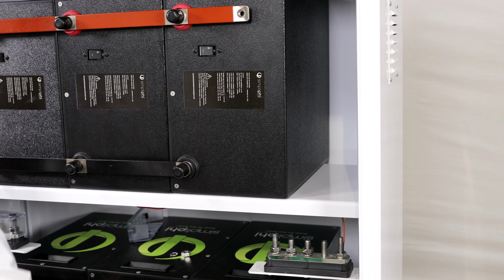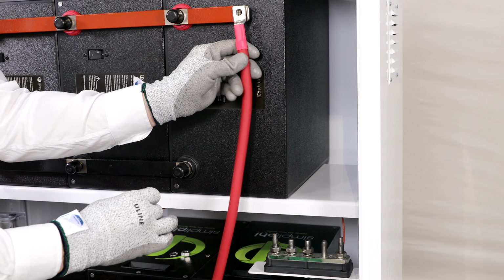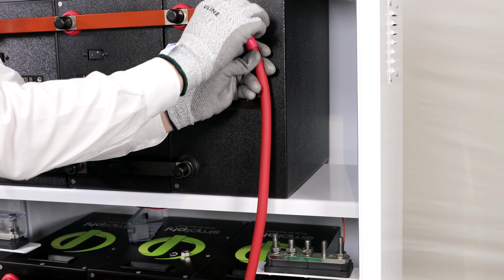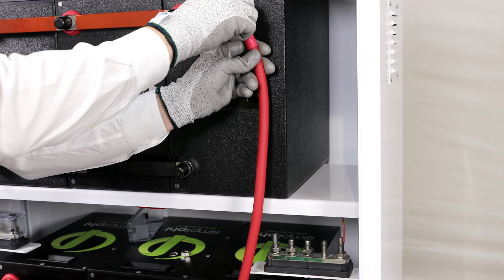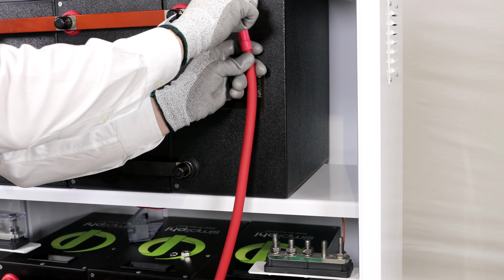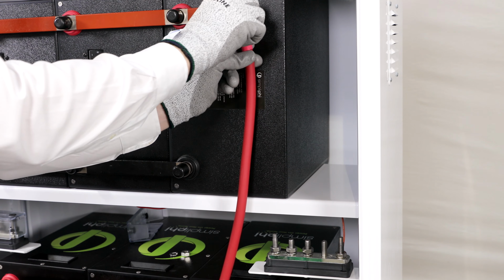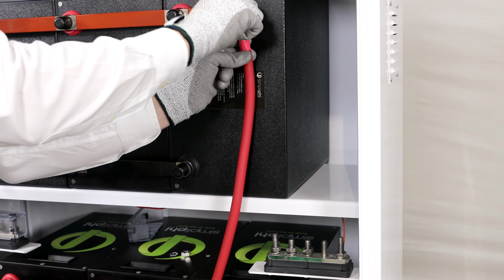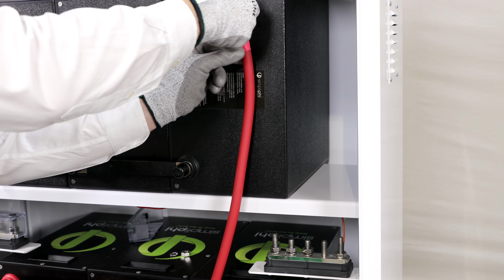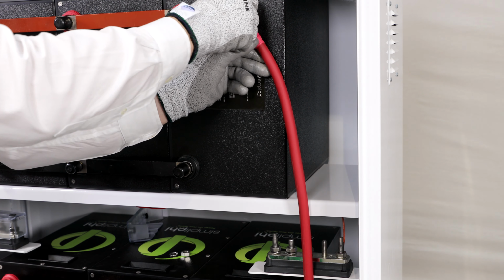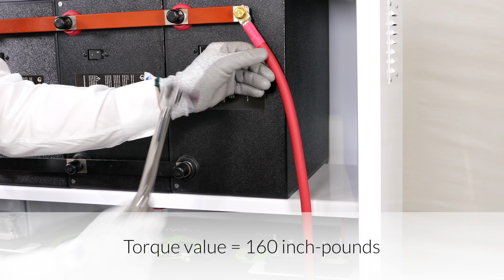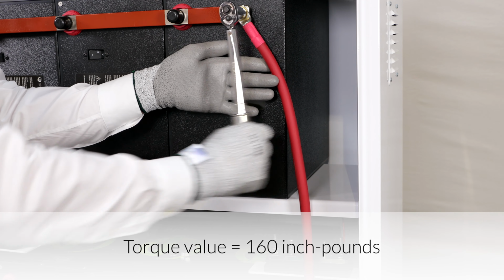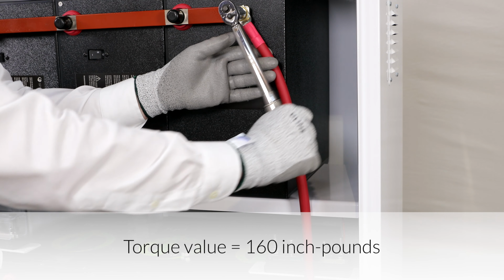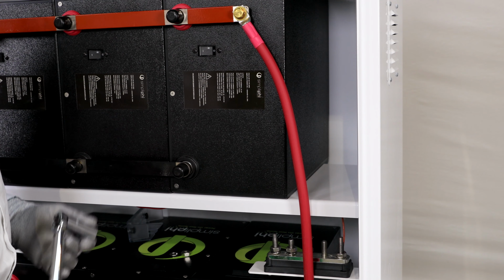Attach the cable at an approximate 45-degree angle when securing it to the bus bar. Angle the cable so it extends toward the 5-point terminal block. This allows the cabling to be routed more easily. Now, secure the cable lug to the bus bar by tightening the brass hex head cap screw to 160 inch-pounds of torque. While tightening, secure the lug with the other hand so that it doesn't twist or move.